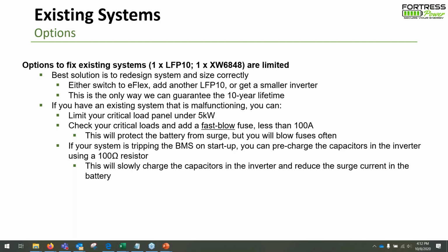This is another problem that we're seeing. On a cold start, the problem is a brand new LFP10 and a brand new XW Pro, for example. The capacitors in the XW Pro have I think 20 or 25,000 microfarads. And when they're empty, they pull a lot of current from the battery. I confirmed this with Schneider. They pull more than 150 amps. So once you start pulling 150 amps from the battery, the BMS of the LFP10 will shut off. And that is why you'll see 4 volts. You'll go from 50 volts all the way down to 4 or 5. And that means that the BMS has been shut off. So to fix this, we can slowly charge the capacitors in the inverter using a 100 ohm resistor.